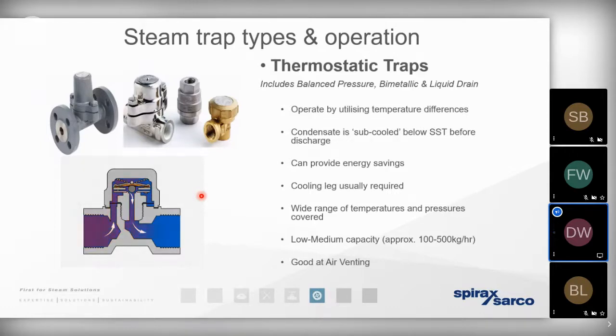And by allowing the condensate to fall by a certain number of degrees, typically anywhere between 10 and 20 degrees, it means that this trap is going to register a fall in temperature. It will open and the steam pressure or gravity will then allow the condensate to drain away where it can be recovered. So this type of trap, it works very, very well if we've got a lot of air that's present within the steam, especially on startup, because it works thermostatically. That air will be allowed to drain away.